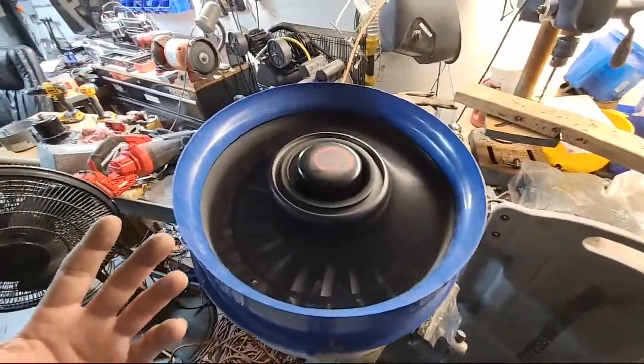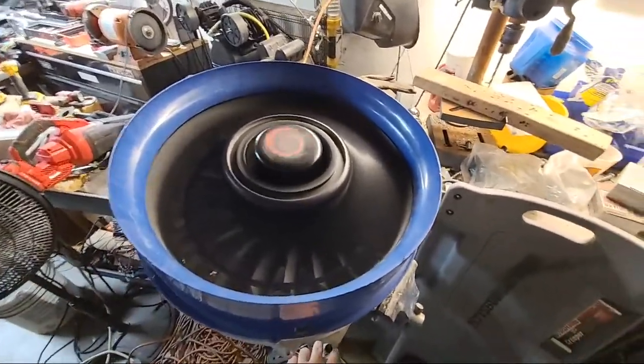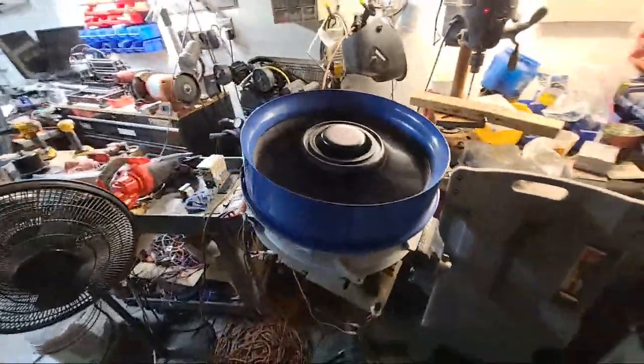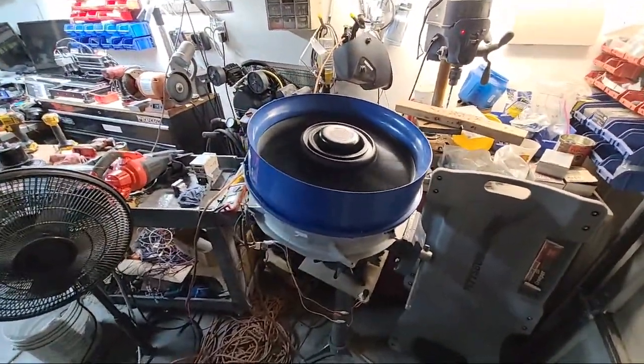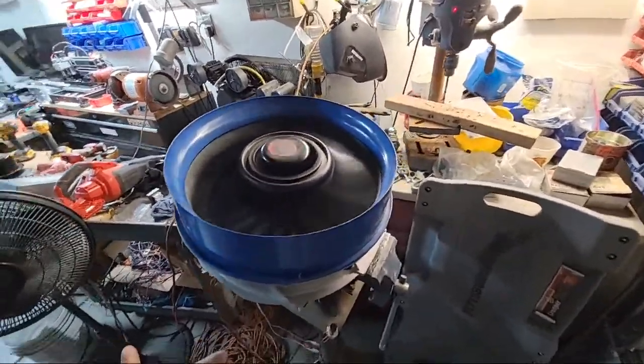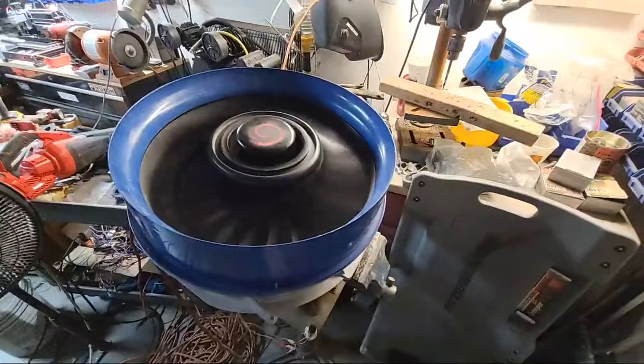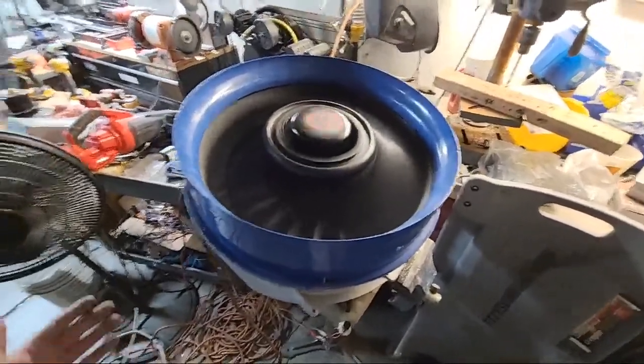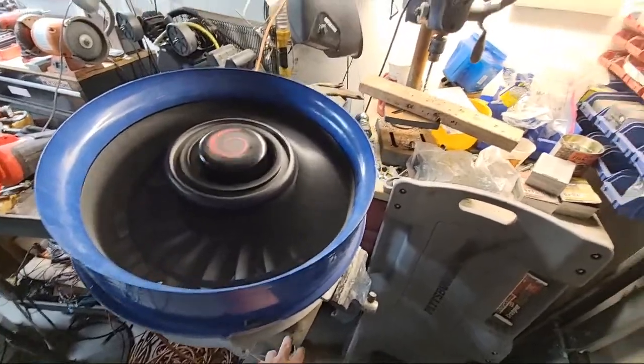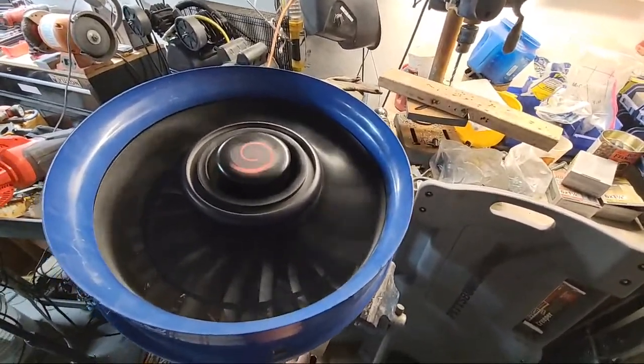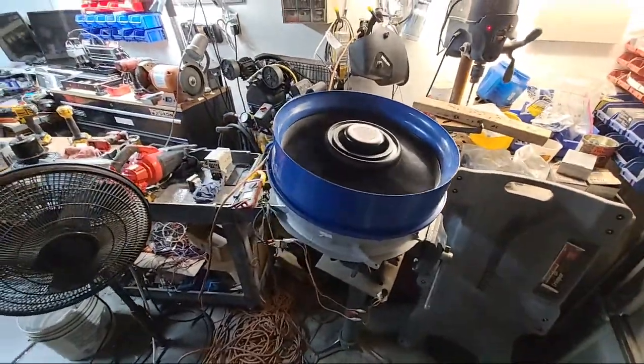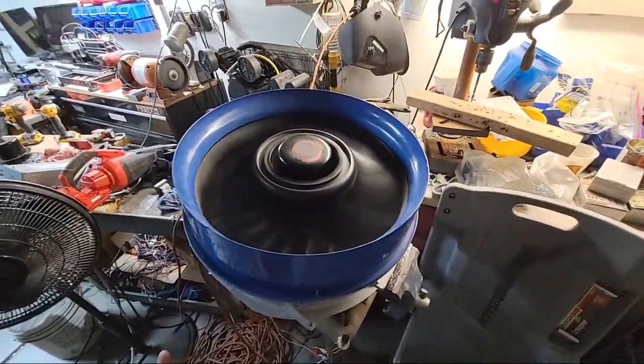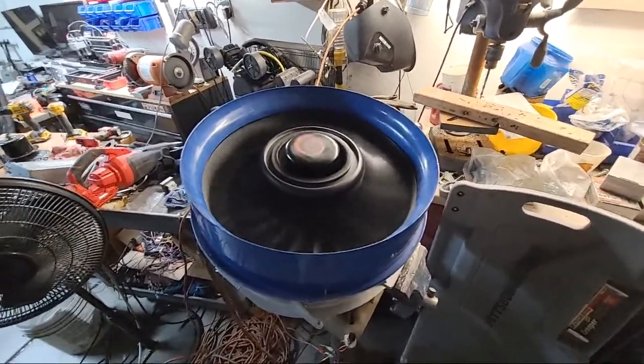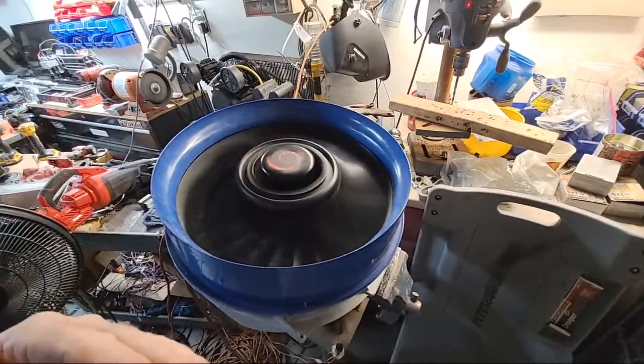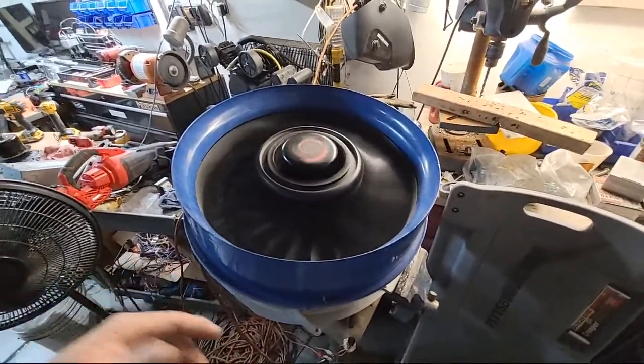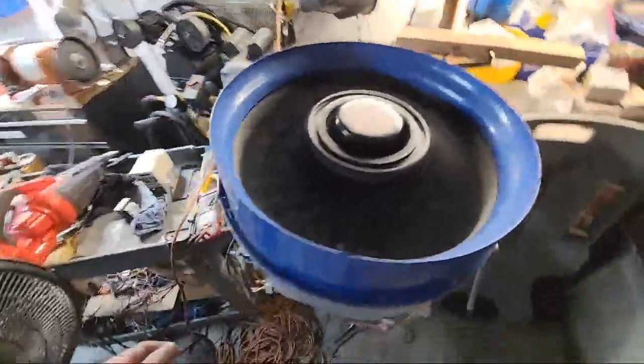These things are basically made for 2-stage, I think what Carrier calls staged air volume. So you adjust it for your full CFMs for the capacity of the unit, 5 tons, 2,000 CFM, whatever. But when it's not on second stage cooling or heating, where it uses full speed, if it's just first stage cooling or fan only, it runs different settings, like 66% is a common setting for something like that. And your amperage of course goes way down. When you drop your blower from full speed to 2/3 of its full speed, it's not 2/3 of current, it's probably like half, maybe even 40% or something.